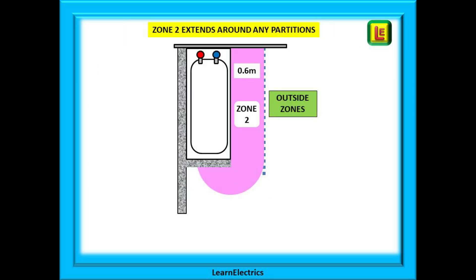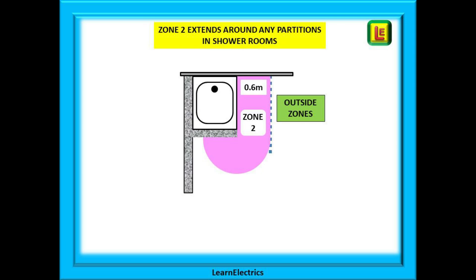Looking at an overhead view of a bathroom, we can see that Zone 2 travels parallel to the edge of the bath and then at the corner of the bath it wraps itself around the partition. Everything beyond is classed as outside the zones. A shower with a footbasin follows exactly the same rules as the bathroom — Zone 2 is 0.6 metres from the edge of the footbasin and then wraps itself around the fixed partition of the shower.